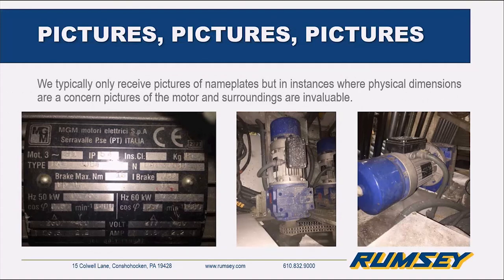Sean adds: just like Jeff showed with motor lead lengths, there's usually some form of a chart in the VFD manufacturer's documentation. But ultimately, between the VFD and the motor, the motor manufacturer takes precedent. There's also a turndown ratio specific to whichever drive or version of drive you're using within a manufacturer — just like there's a turndown specific to the motor. So those are a couple of things you need to match up based on what your application is.